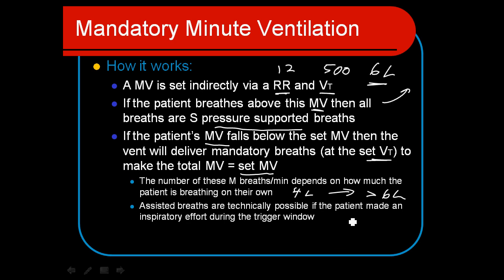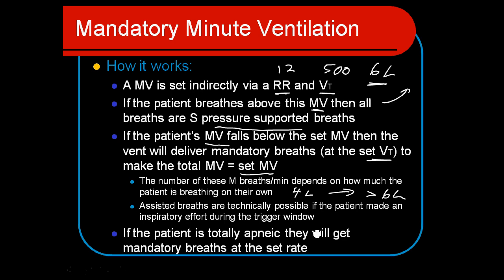You can get anything from zero to 12 breaths per minute to augment or mandate the patient's minute ventilation. If the patient is totally apneic, they'll receive the full mandatory breath rate — in this case, 12 breaths per minute.